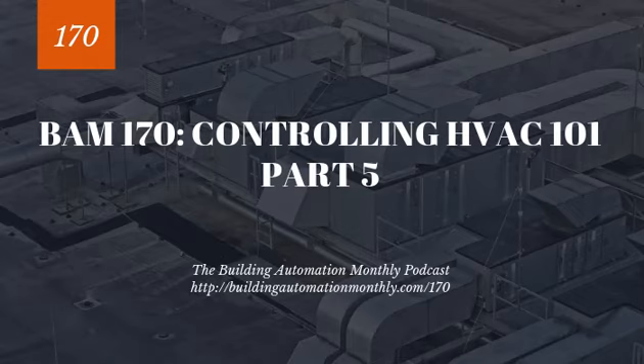And low DeltaT is when the delta between two temperatures, the difference between two temperatures, is too low. And basically what happens is you're not transferring BTUs. So what's going on is that we want to make sure we're drawing enough from the primary and we are still maintaining that 10-degree differential. And I'm talking chilled water side here. Obviously, boilers are going to be a little bit different as far as their temperature delta between primary and secondary. So I'm mainly focusing on chilled water here. It's basically the same principle, just bigger deltas. But with that being said, DeltaT can actually cause issues where we are not getting a good exchange across our coil. You can actually be sitting there and not pulling enough out of the primary.